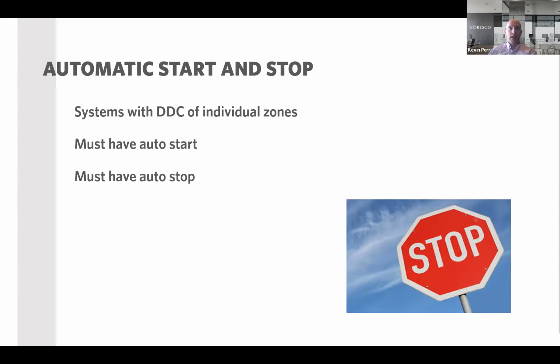So systems that have DDC controls and individual zones need to follow this. Any HVAC system with individual zones needs to, based on thermal lag and acceptable drift, stay comfortable in that space. It's going to start to set back the occupied set point by at least 2 degrees based on those calculations. I know that there's one building in downtown Denver that I regularly have meetings in, and it does exactly that. This isn't a new building by any means, but come 4:45, you can tell the HVAC system is turned off because the low humming of the fans throughout the day has now shut off and is letting the temperature drift for the last 15 minutes of the day. So that is something new, this automatic stop that needs to be incorporated.